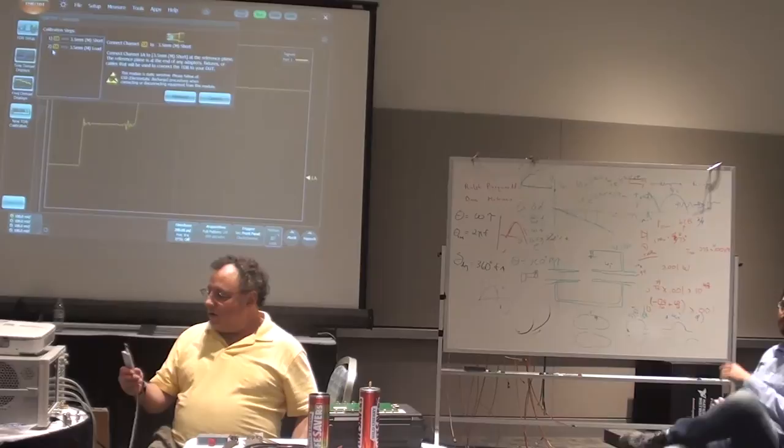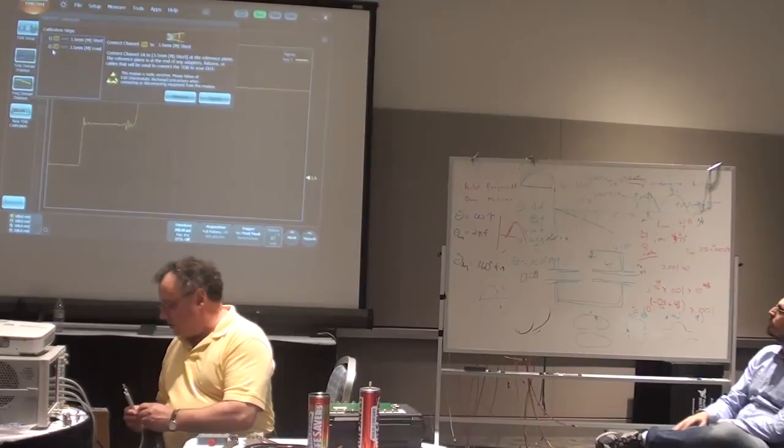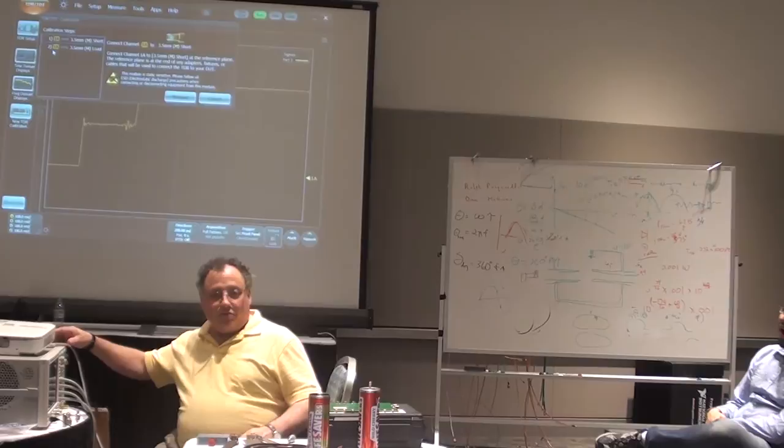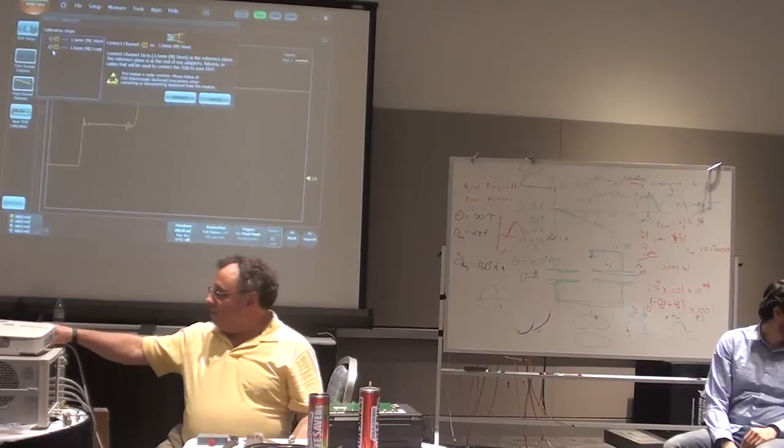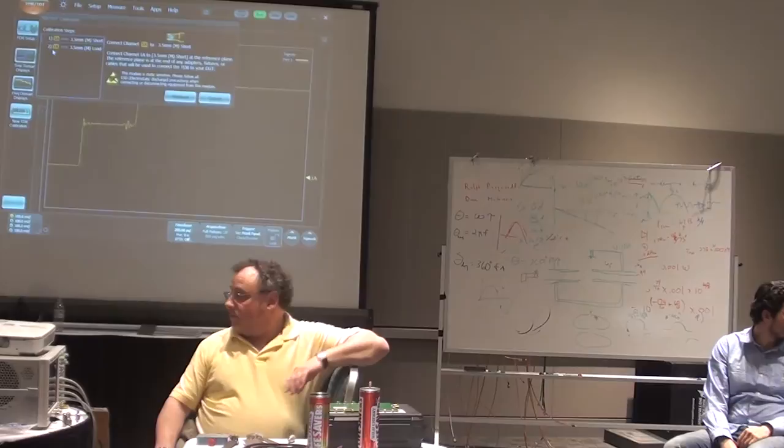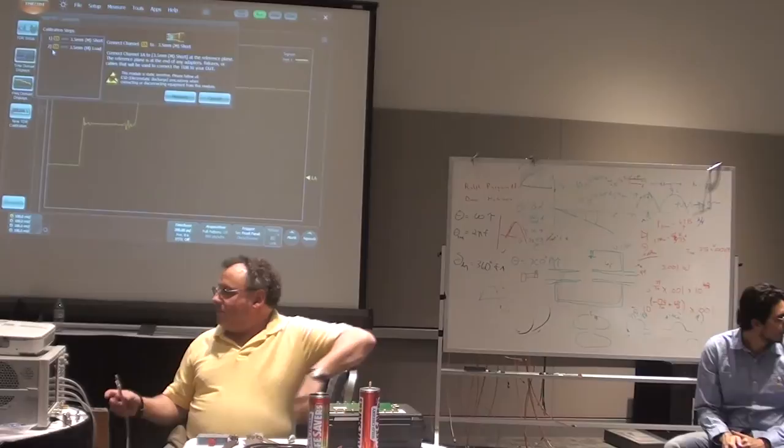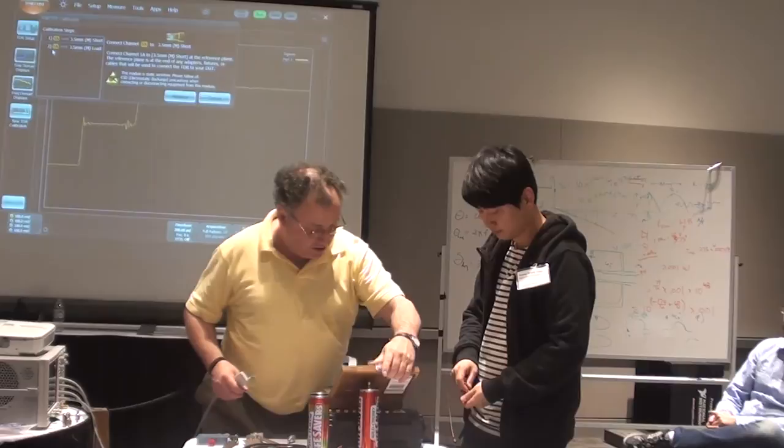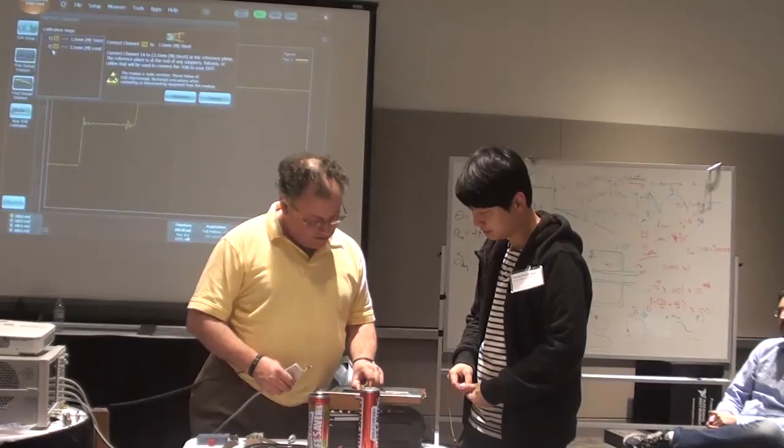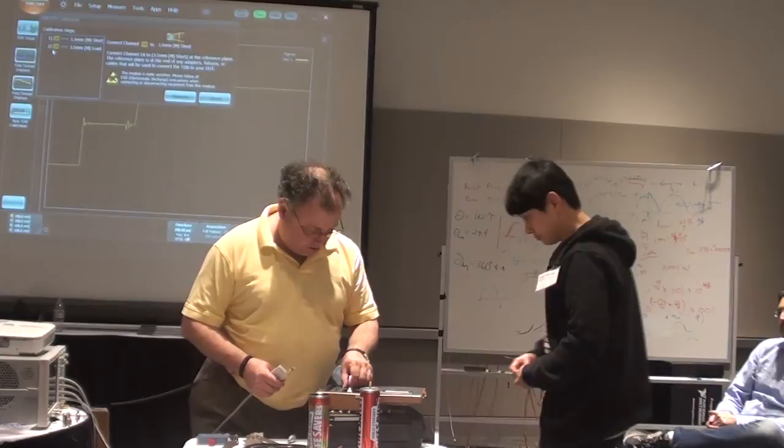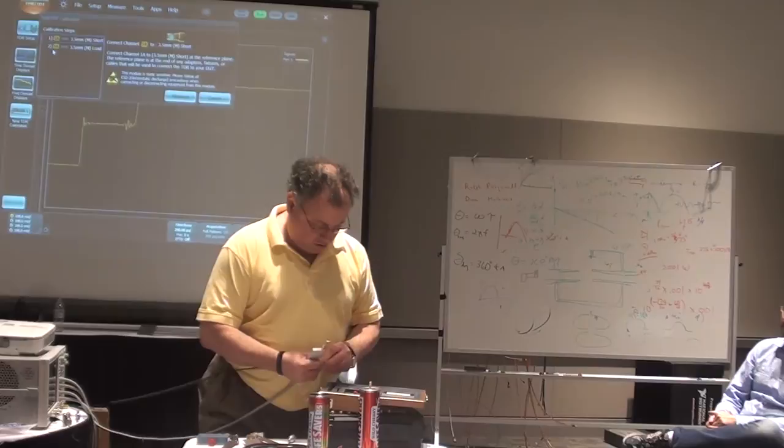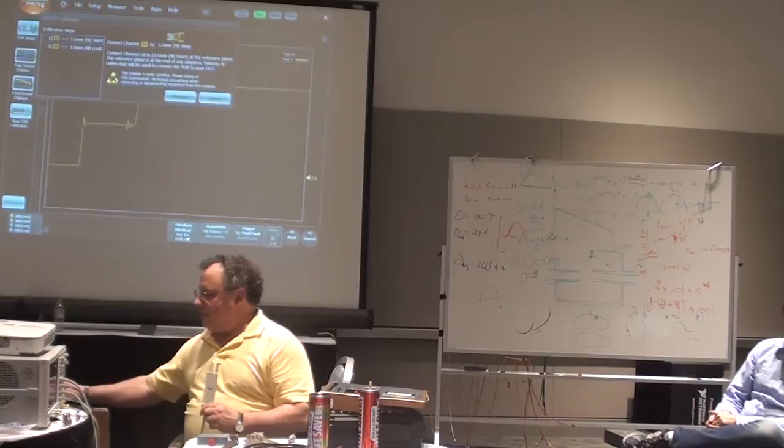But it is only that. As you want to go to much higher frequencies, the diameter has to get smaller, so you do not get waveguide modes on the coax. Okay, so now when we're at this point here, we're ready to put our calibration standards on there. And you can use any one of the SMA cal kits, and it's just putting your open and short on there. And you have to do it in the sequence they're asking you to do it. Let me, just for giggles, I'm going to use a cal kit. I don't have a cal kit with me right here. Who has one of the SMA cal kits? I just need a short and an open male. So you don't have to tell which kit you're using? We're going to get there. Maybe I went through that kind of quick. It does ask is that thing of e-cal not there? I'm just going to be using generic cal kits. So then I don't have to worry about any of the other gory details. That's a load. I need the short circuit then. That's an open. There's the short.